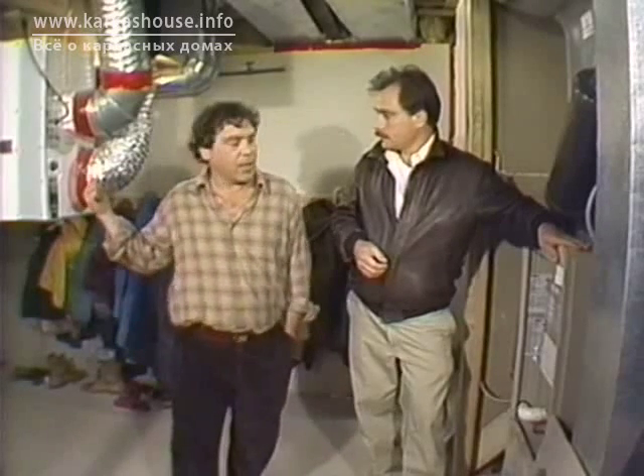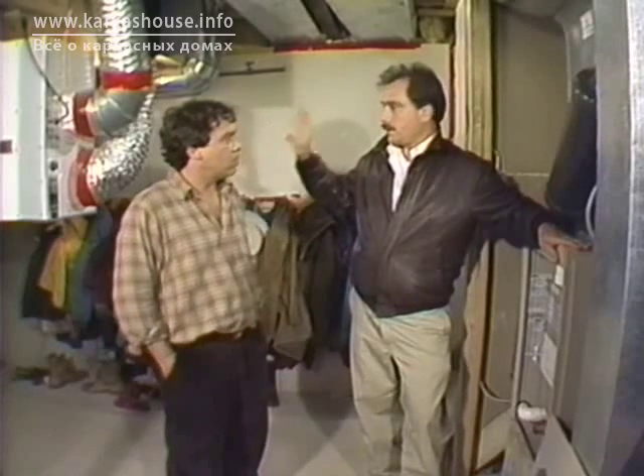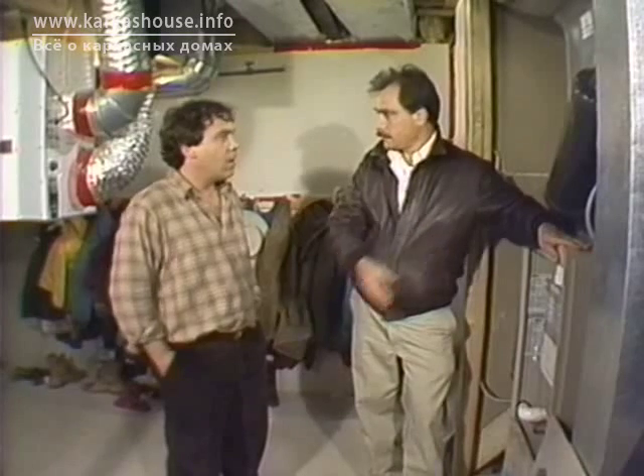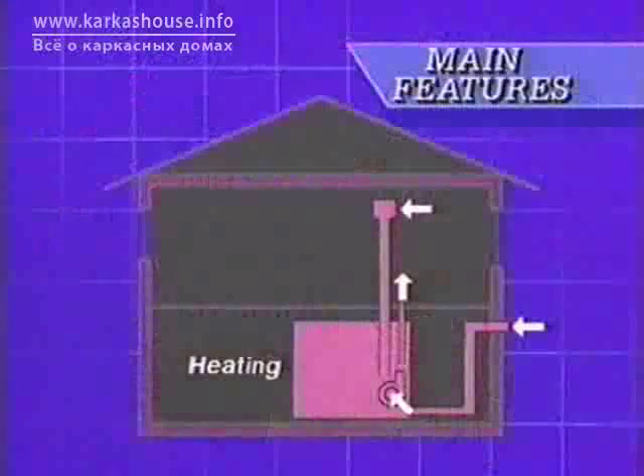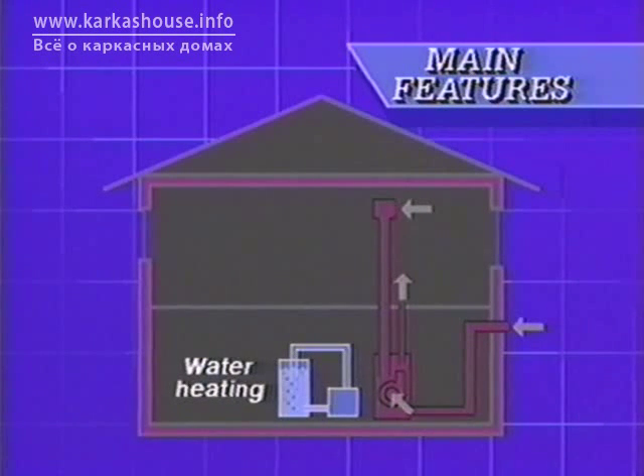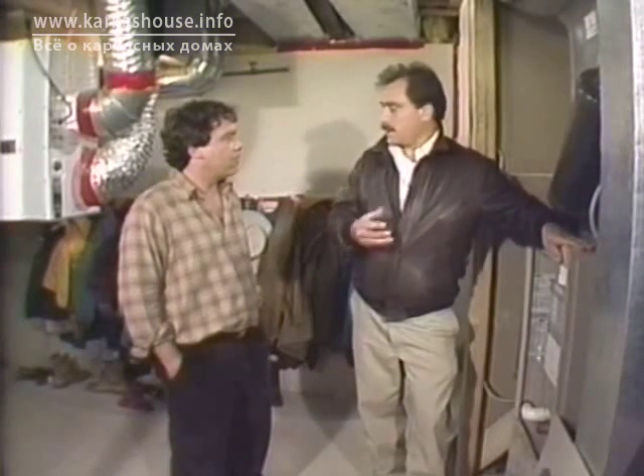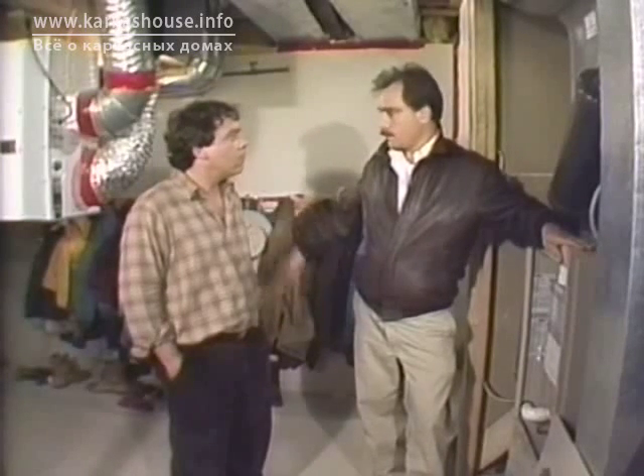Well, does the mechanical ventilation system also supply combustion air for the appliances? Adamantly not. The mechanical ventilation system is in the building only to supply quality air to the occupants of the building. Any quantity of air that's required for combustion equipment must be delivered to that equipment itself. Are there any other overall considerations for the R2000 heating system? Well, because it can be so much smaller than conventional heating systems, there are lots of innovative approaches you can take. We've seen buildings in which hot water tanks have been used as the backup heating system, which is really quite neat. But the most important thing in selecting any mechanical device for an R2000 house is health and safety, and we're going to be looking at a whole bunch of those things in future programs.